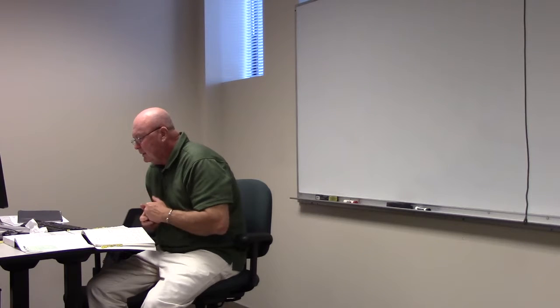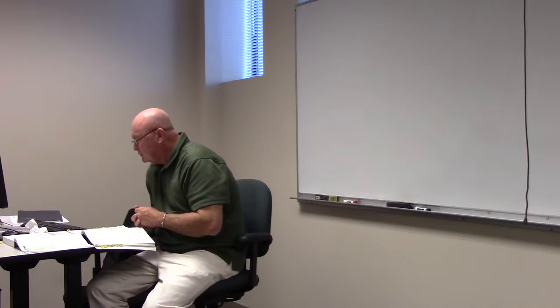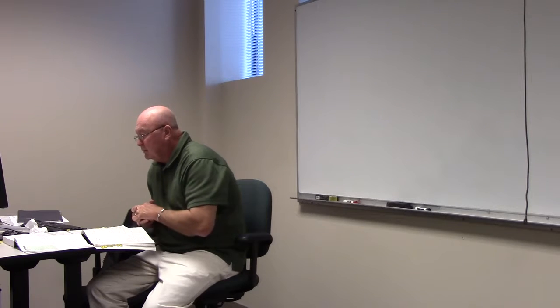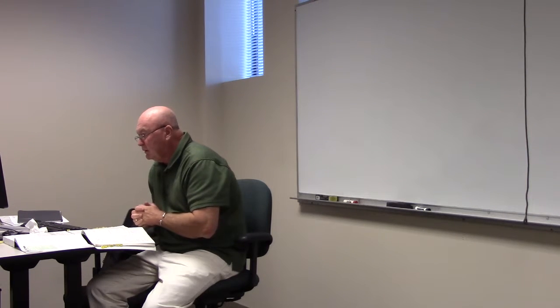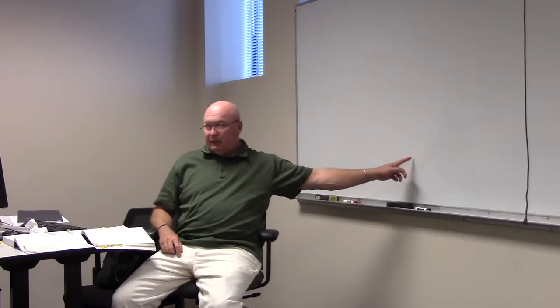Reading on, each load must be designated as either continuous or non-continuous. Continuous is going to be a multiplier of how much percent? How much is a continuous load? What I just wrote down up here a minute ago. What's your multiplier going to be for a continuous load? 125%. I'd write that down somewhere. Continuous load, 125%. Okay? You got something to write with? Okay. Continuous load, 125%.